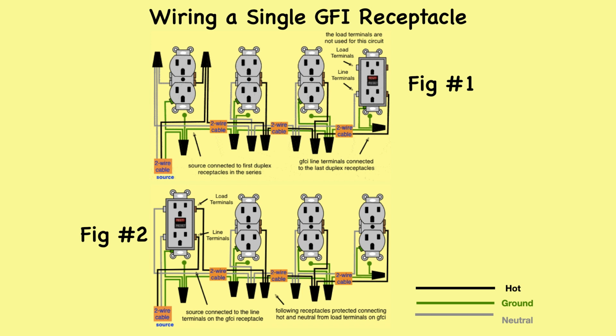In figure number 2, one ground fault circuit interrupter protects multiple duplex receptacles coming after it, known as multiple location protection. 2-wire cable runs from the GFCI to all the following outlets. The line terminals on the GFCI are connected to the circuit source and the load terminals are connected to each following outlet with a pigtail splice. This keeps each duplex receptacle connected directly to the GFCI.